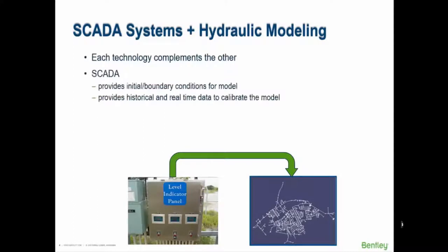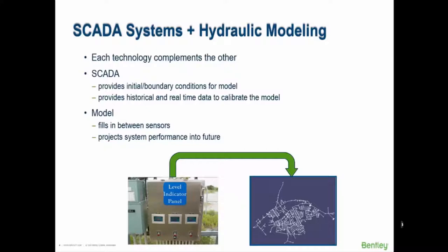These technologies complement one another. The SCADA system can provide initial conditions and boundary conditions for the model. It can provide historical patterns you can use to compare the model to for calibration. And the model can fill in between sensors, tell you properties the SCADA system isn't measuring, and most importantly, project what's going to happen in the future. SCADA systems just can't do that, and this can be so valuable to the operator. Unfortunately, in many cases operators and modelers are in two different silos — we need to break down those walls.